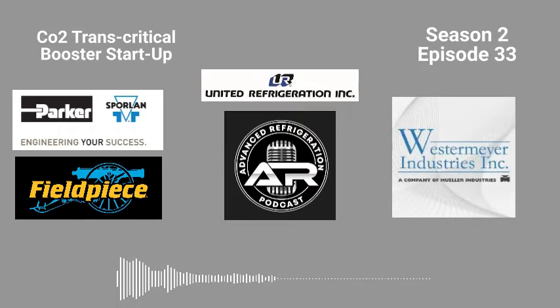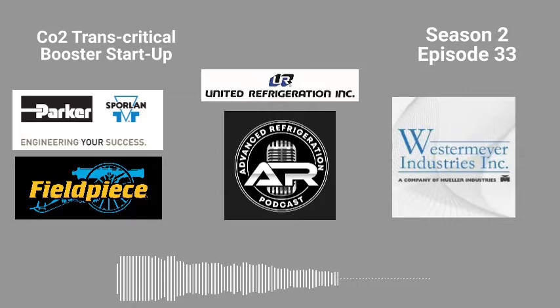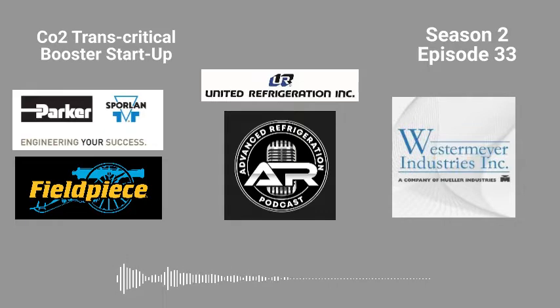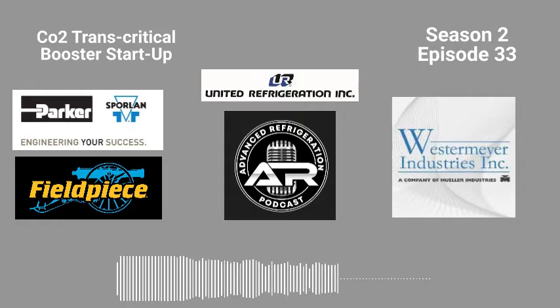Did anyone go through the wiring at all? Oh God, no! Really? No, I meant with the company that you work for. No one went there to check out the wiring? Check out what wiring? The wiring on the rack before they started up. Well, it's all going to be wired wrong no matter what. Well, it's pretty hard to check the wiring when you've got no controller. Oh, really? So the rack doesn't have a controller either? The rack showed up with no boards. I'm not kidding you. Yep, we had sent all used boards out of another store.